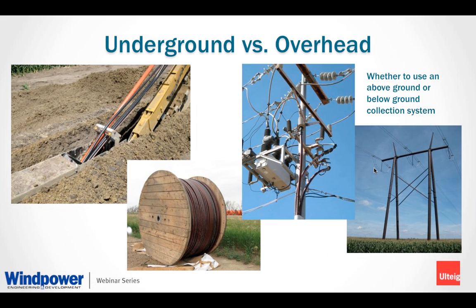One last thing to look at for overhead conductor is if you have a tremendous amount of overhead line, we've seen typically in wind farms that it introduces reactive power needs throughout the wind farm. And depending on your interconnect requirements, this may have a need for additional cap banks to compensate for that. With underground cables, we don't see this happen as often, as they tend to be more capacitive than overhead cables.